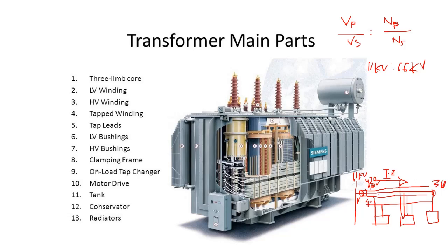Now this particular task is done in the transformer using tap changers. The term tap changers means that in the secondary you normally have a winding, and you have a tap that you can attach to the winding. By changing this tap to different locations, you can control the number of turns. That means you can control the output voltage. So this is called tap changers.